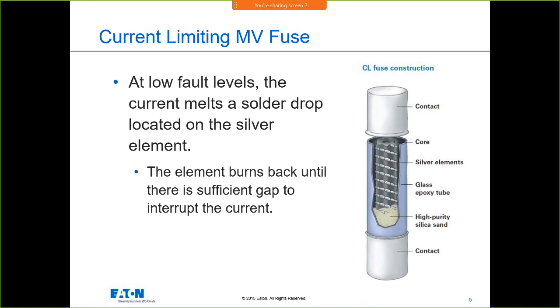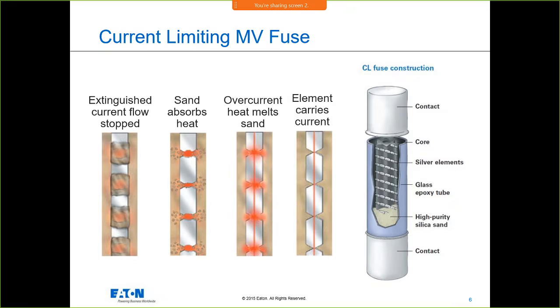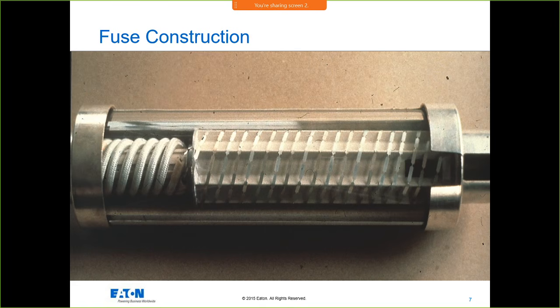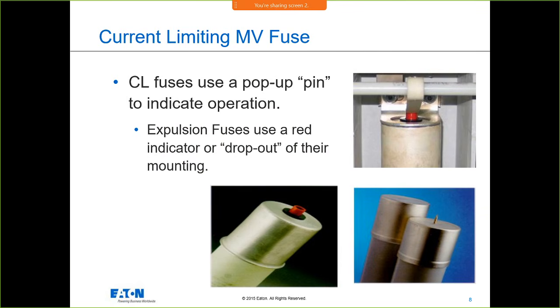The element burns back until there's sufficient gap to interrupt. Basically, you have the same deal that you have with regard to the low voltage power fuses. That element will turn to fulgurite and it'll isolate on short circuits. There's your helical. You can see a nice fuse construction picture in here. And then you have the pop-up that'll give you the indication on whether that fuse is opened.